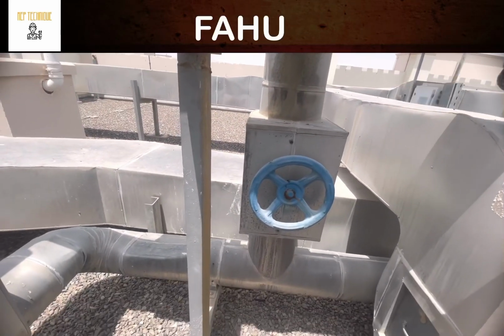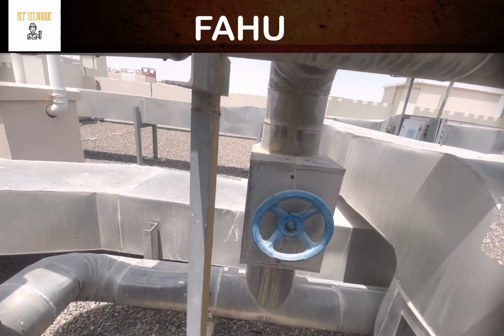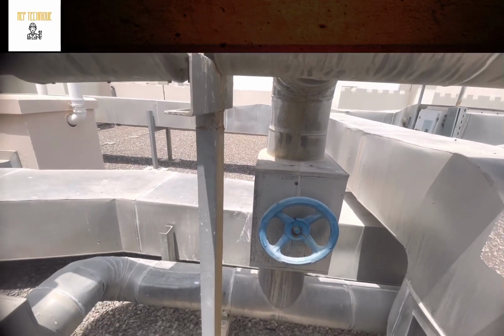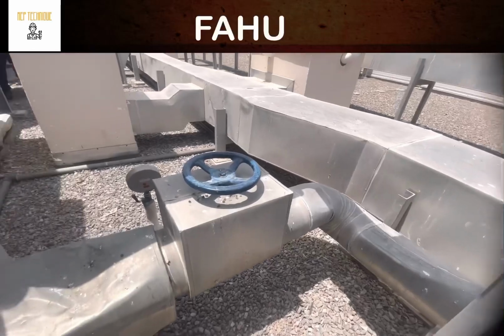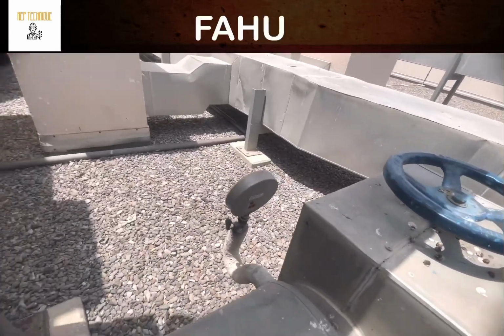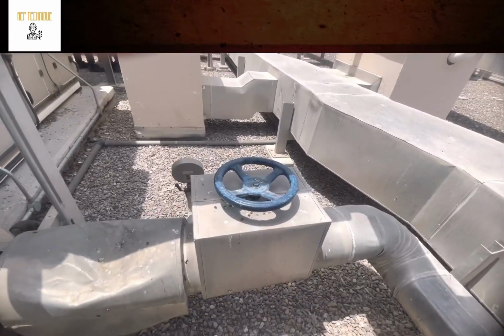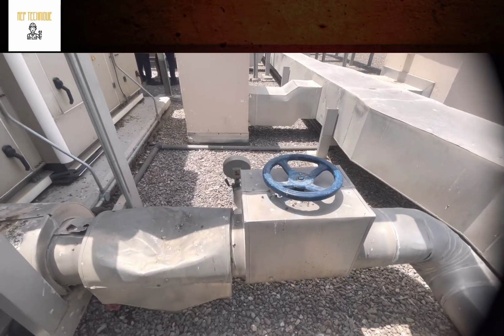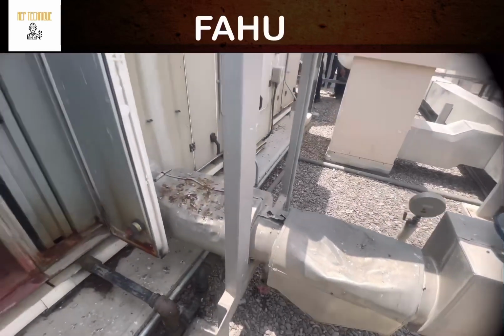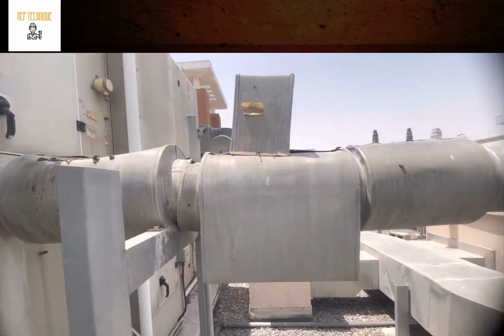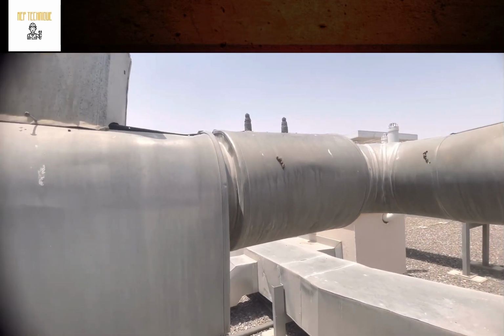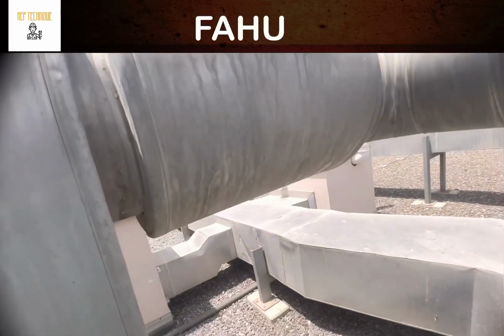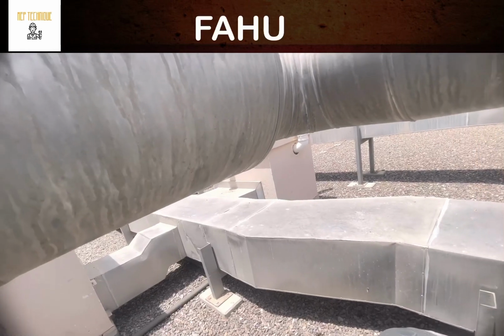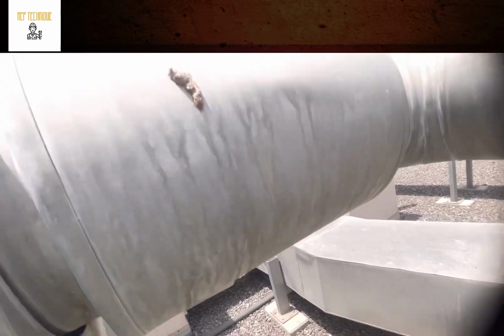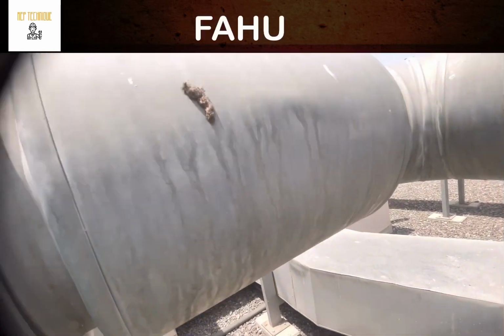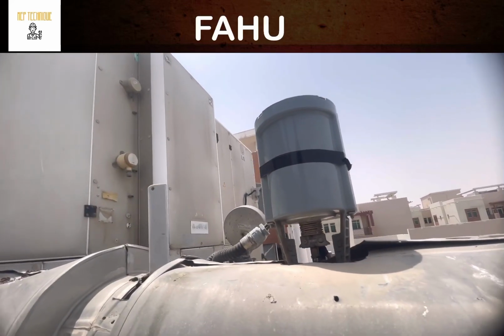The bypass valve is required for flushing, back flushing, forward flushing, and maintenance of the FAHU. This is the pressure gauge, and you will get to know the pressure. This is a butterfly valve, with which we can isolate and regulate our chilled water. And this is the chilled water return line. These are the DRV, double way regulating valves, for balancing the chilled water. And this is the actuator valve, with which we can control the chilled water.